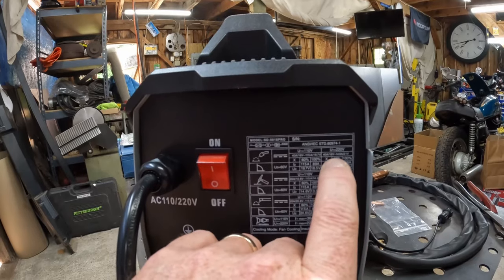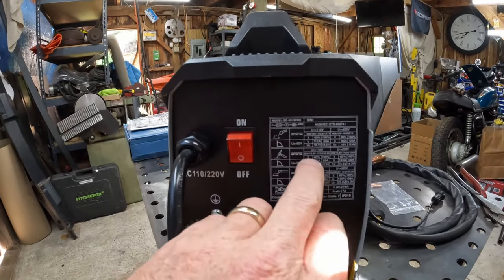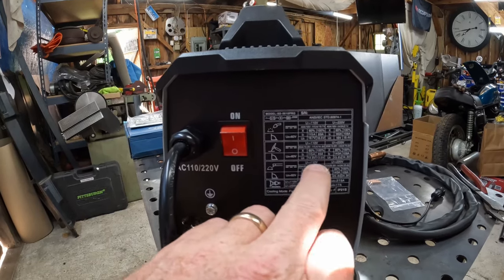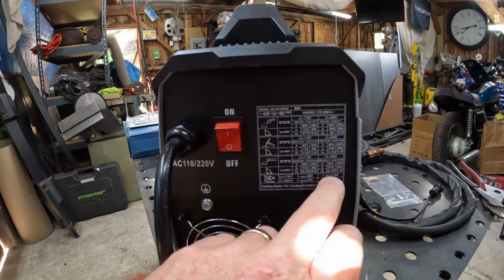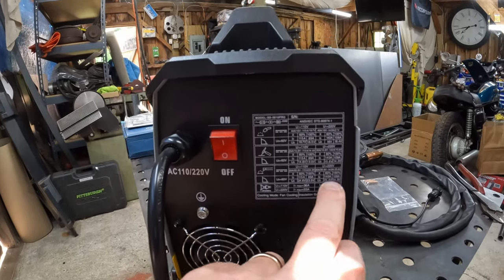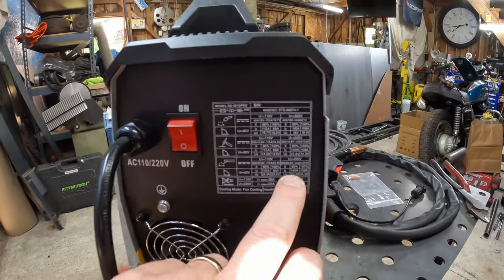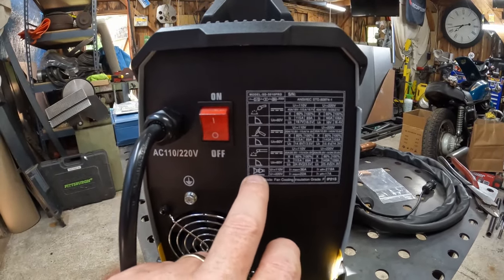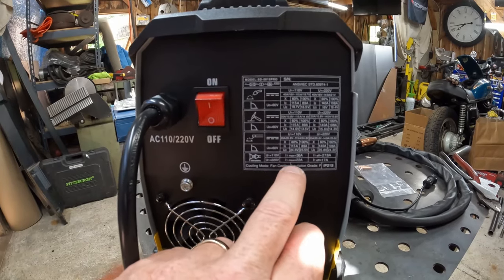On 220, you get 140 amps at 60% and 108 amps at 100%, with 40 amps draw. For TIG, it's 20 amps draw either way — 110 or 220 — giving you the full 140 amps on TIG. Stick is also 20 amps draw: 140 amps at 60%, 108 amps at 100%. For MIG, max draw is 36 amps at 110 fully cranked up, and 22 amps at 220. Keep that in mind when selecting a circuit and circuit breaker to plug this into.